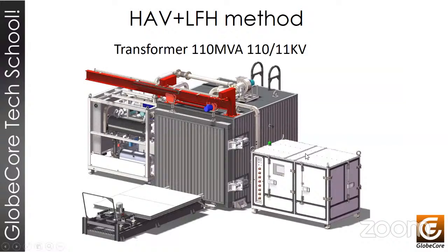Now, let's focus on the same vacuum oven, only in combination with the LFH heating system. The difference in operation is that we will heat the windings concurrently in a combination of two heating systems. That will speed up the heating process. Further down the line, after the first cycle, we will maintain the winding temperature by means of the low-frequency heating system. That will reduce the number and time of activations of the electric plate heating system.